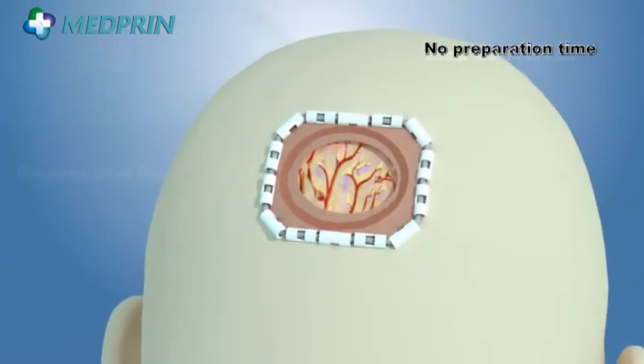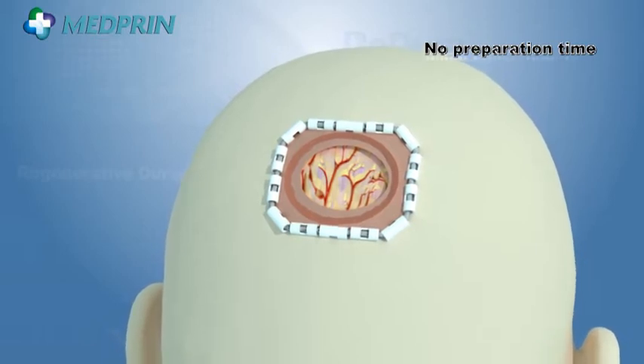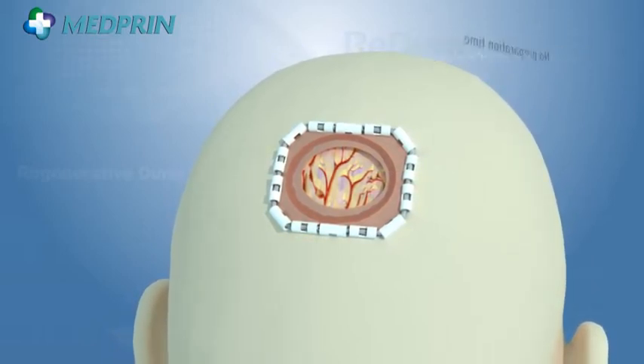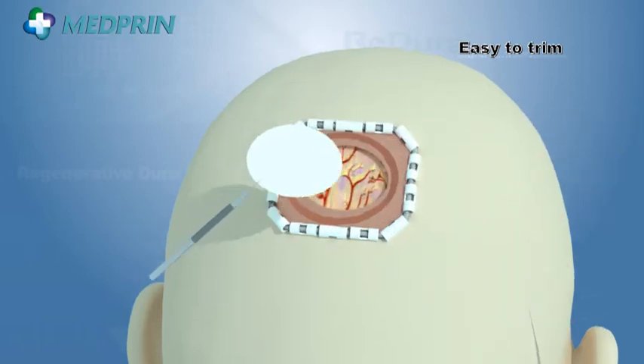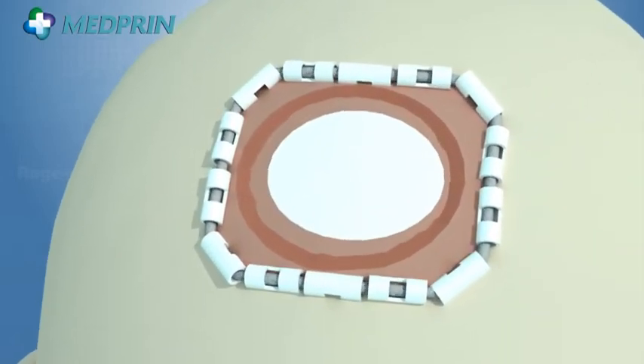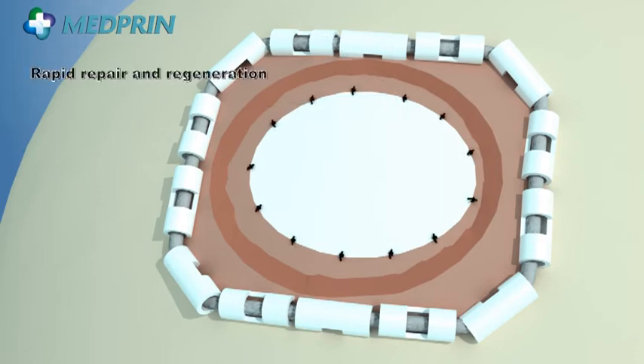Prior to application, ReDura doesn't need to be soaked in sterile physiological saline solution. ReDura can be easily trimmed to the desired size and shape. It is recommended that the ReDura implant overlaps the Dura defect by approximately 1 cm.